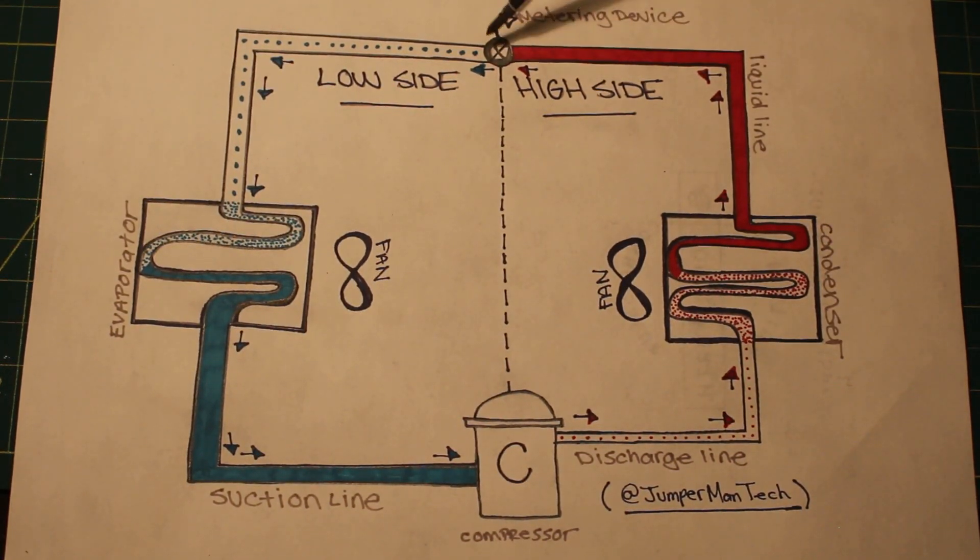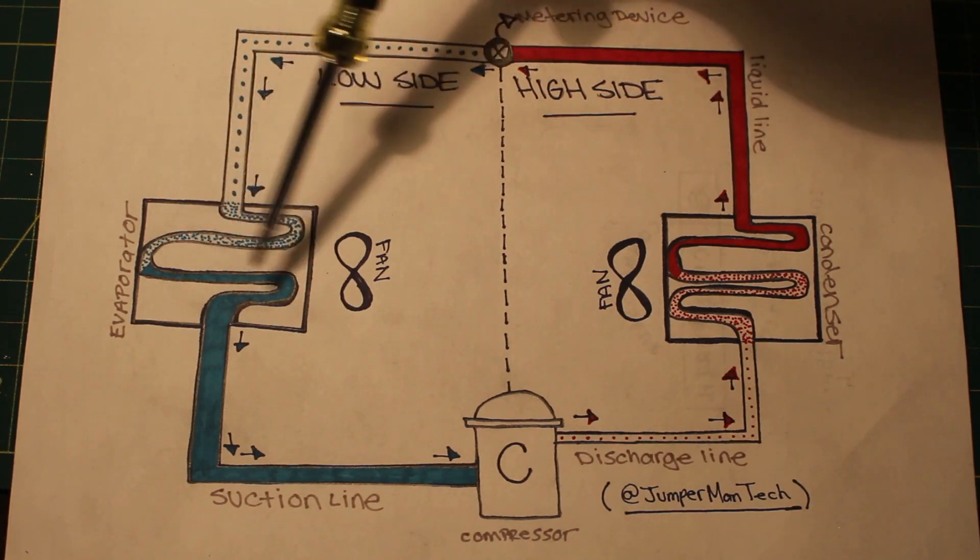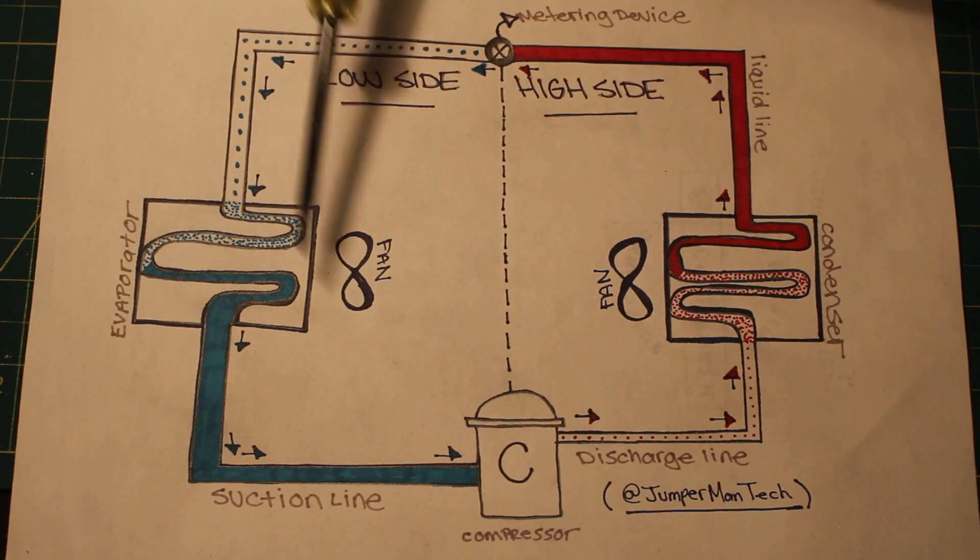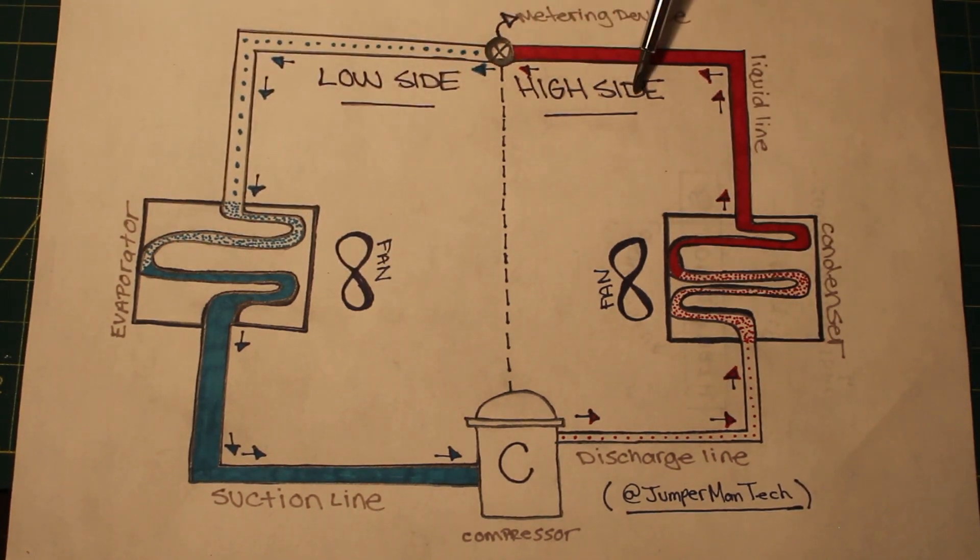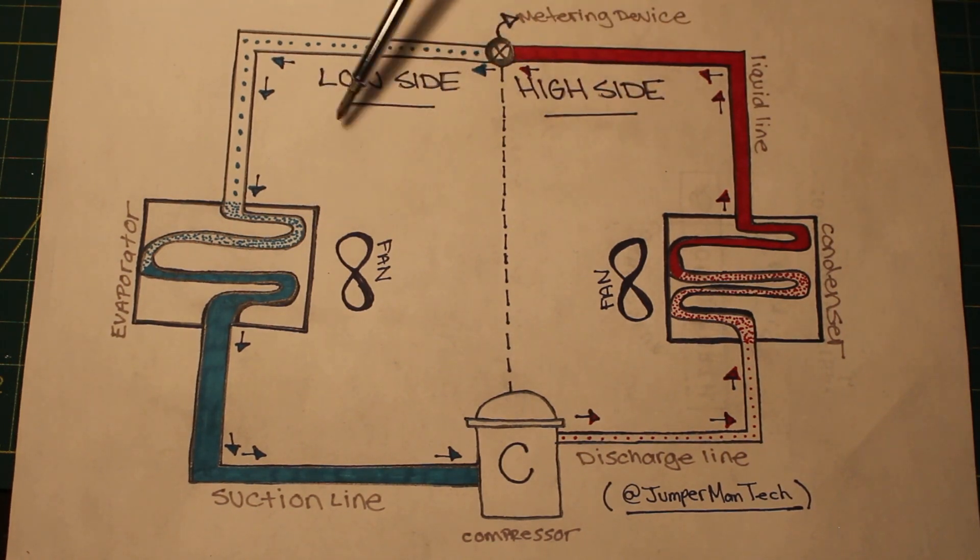Refrigerant next enters our metering device, where there are many types, but its main purpose is to distribute proper amount of refrigerant into our evaporator. If we look at our diagram, we have a low side with our evaporator and a high side with our condenser. Our metering device is what divides the system from the high side, where we have high pressure, and the low side, where we have low pressure.